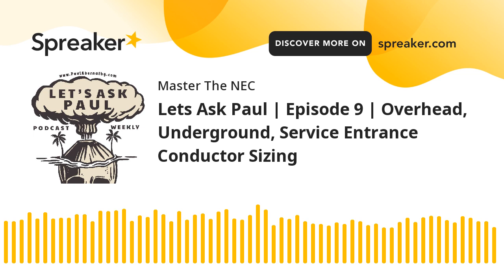Now, exception number 3 is where it says 2 to 6 circuit breakers or sets of fuses shall be permitted as the overcurrent device to provide the overload protection. The sum of the ratings of the circuit breakers or fuses shall be permitted to exceed the ampacity of the service conductors, provided the calculated load does not exceed the ampacity of the service conductors.